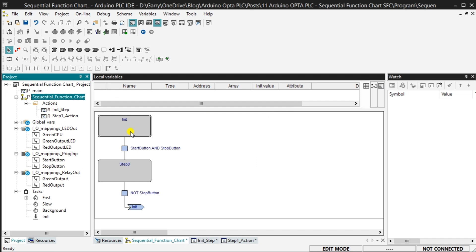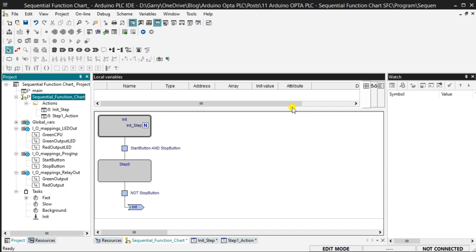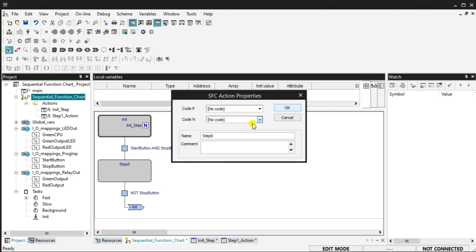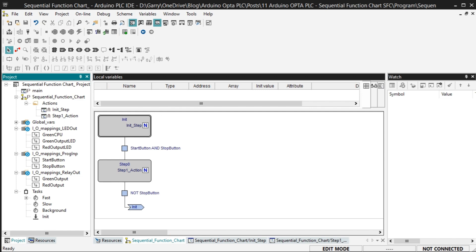We now have the basic structure and sequence for our SFC program. However, we have not specified the actions to be taken at each step. Double-click on the init step. The SFC action properties window opens up for the step. Code P means pulse. The action is executed only once per step activation, regardless of the number of cycles the step remains active. Code N means non-stored. The action is executed as long as the step remains active. In our case, we will use code N on our init_step logic. Double-click on step 0 and use code N as well on our step 0 logic. Our SFC Opta PLC program is complete. Save the program.